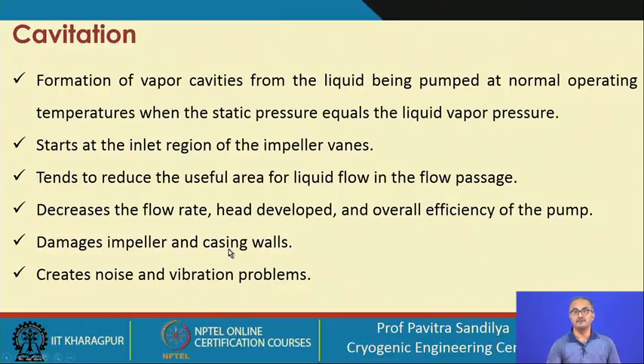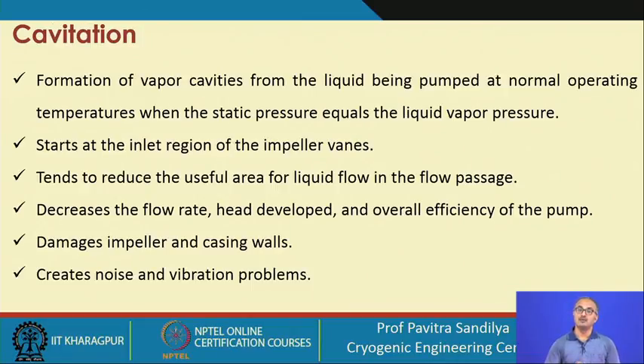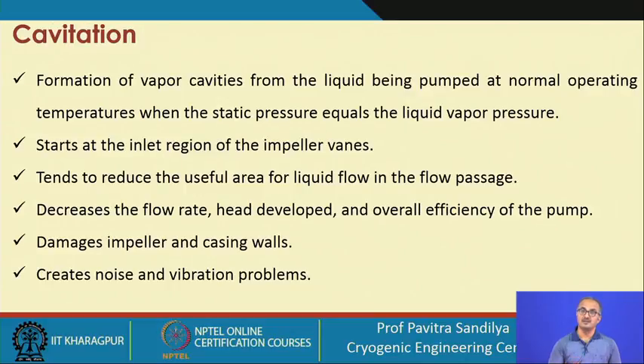Now we come to a very important phenomenon that dictates pump operation — cavitation. Cavitation means the formation of vapour cavities from the liquid being pumped at normal operating temperatures when the static pressure equals the liquid vapour pressure. Any liquid will vaporize when its vapour pressure becomes equal to the surrounding pressure. If the static pressure equals the liquid vapour pressure, the liquid starts boiling off, forming bubbles — and this formation of bubble cavities is the cavitation phenomenon. It starts at the inlet region of the impeller vanes.